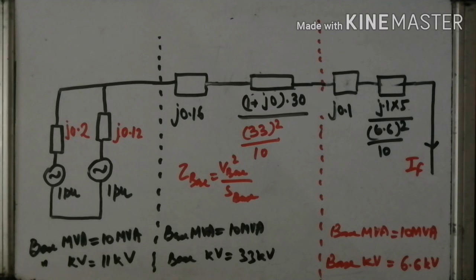right? Once again I am repeating here, after taking the base values of MVA, which is same throughout the circuit, and kV rating, it depend upon the voltage ratio of the transformer, that is 11 kV, 33 kV and 6.6 kV. These are the sections. Okay, now to calculate the fault current, it is necessary to make a Thevenin equivalent circuit, right? To make the Thevenin equivalent circuit, first of all find out the open terminal voltage, then after impedance of the circuit, then we can calculate the IF. Okay, now go to the question.